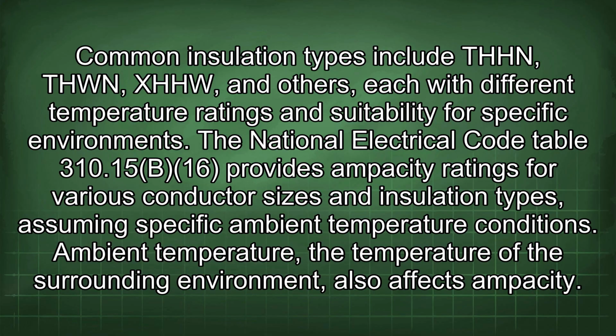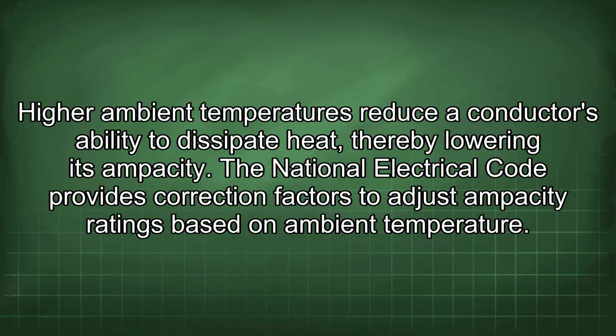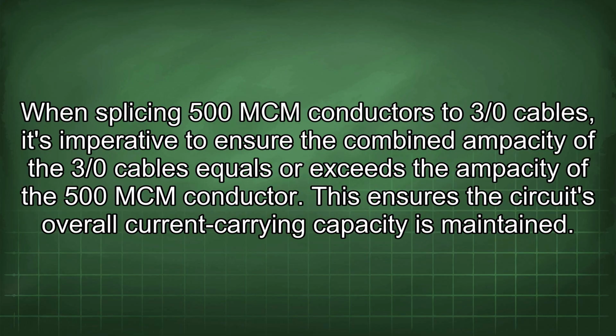Ambient temperature, the temperature of the surrounding environment, also affects ampacity. Higher ambient temperatures reduce a conductor's ability to dissipate heat, thereby lowering its ampacity. The National Electrical Code provides correction factors to adjust ampacity ratings based on ambient temperature. When splicing 500 MCM conductors to 3/0 cables, it's imperative to ensure the combined ampacity of the 3/0 cables equals or exceeds the ampacity of the 500 MCM conductor. This ensures the circuit's overall current carrying capacity is maintained.